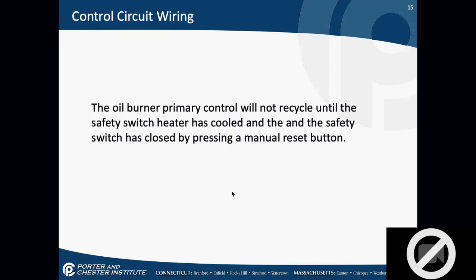The oil burner primary control will not recycle until the safety switch heater has cooled and the safety switch is closed by pressing a manual reset button. Okay, now this is extremely important. Every time someone presses a manual reset on an oil burner control, like the one I just showed you, it has a manual reset button on it. Every single time someone presses the manual reset, the burner starts. The ignition transformer starts. If there's a solenoid, that solenoid opens and allows fuel from the oil tank to be sprayed into the combustion chamber. If the flame does not ignite, that fuel is still in the combustion chamber, puddling at the bottom of it.